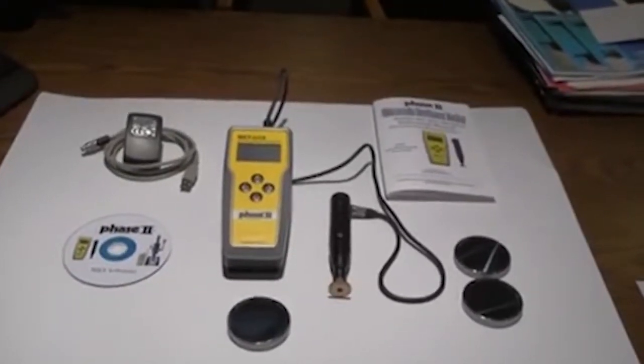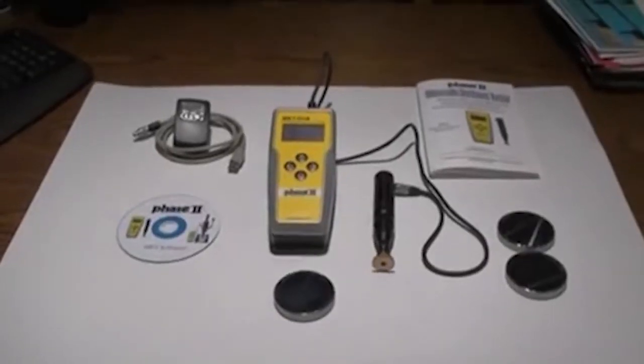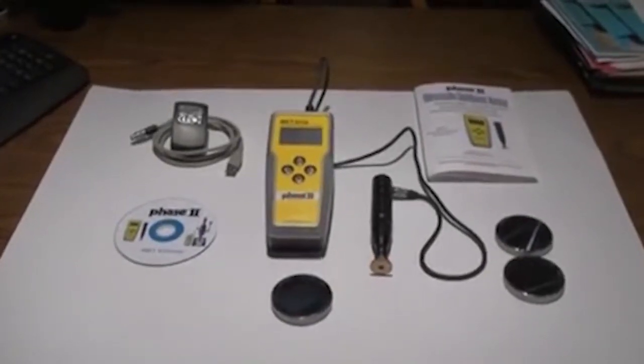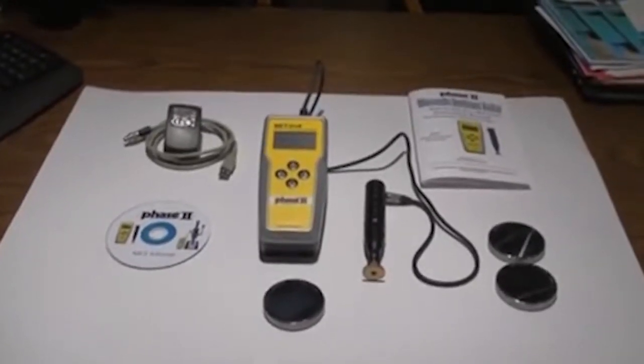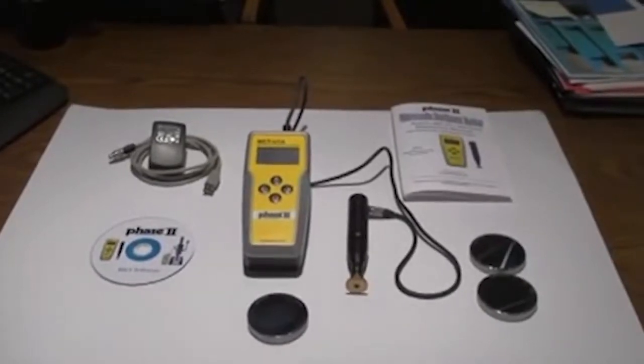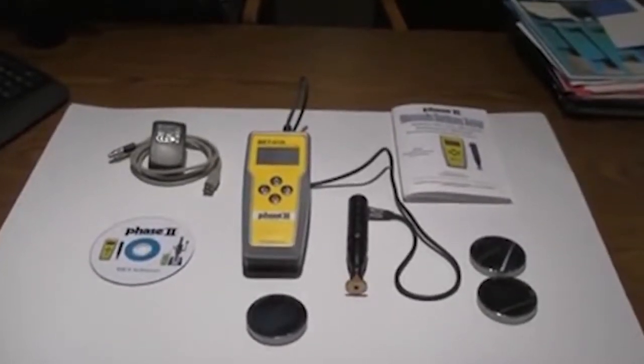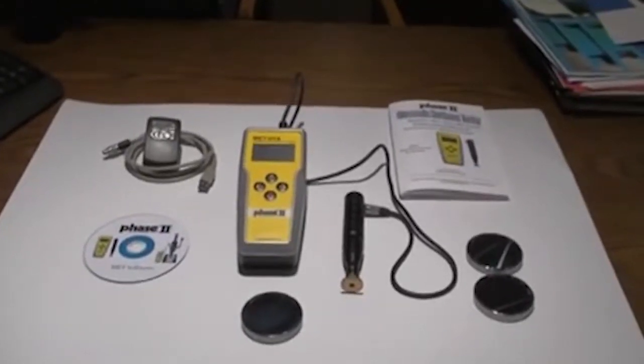It can do so non-destructively unlike most other portable hardness testers. The technology incorporated is based on the UCI method of hardness testing. UCI, or ultrasonic contact impedance, is the measurement of the frequency shift of a resonating rod tipped with a Vickers diamond after applying a fixed force against the surface of the part to be tested.